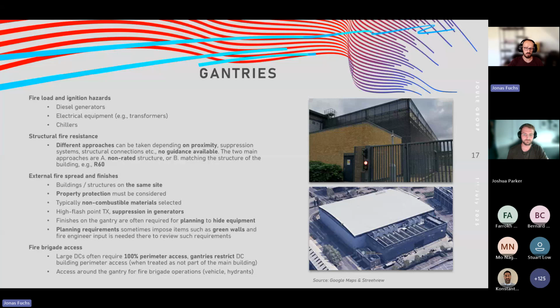Often with data centers in cities, planning permission requires hiding equipment and making gantries more visually appealing, so selecting materials to enclose the gantry is important to avoid introducing more combustible material to the site. Planning requirements often also call for green walls on the gantries, which are themselves a fire safety topic: they can contribute to fire spread, and their construction often involves membranes and plastics which, especially during drought, can increase overall fire load and create an undesirable condition for the site.